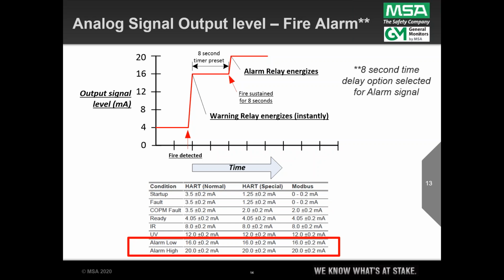Now I did want to mention, if you go down to the table below, I put a box around the instant and the timed alarm relays, but right above those two, there's an 8 milliamp level for IR only, or infrared energy only. And then there's another 12 milliamp plateau or level that says I'm seeing UV only. So those are the two pre-alarm levels that the FL500 offers. I didn't actually put that into the graphic, but I wanted to mention that those are there.